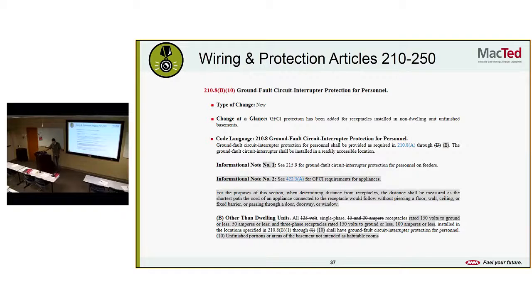More ground fault. Ground fault has been added for receptacles installed in non-dwelling unit unfinished basements. So now if you have a basement, even if it's not a dwelling unit, you have to have GFI protection in that. So all single phase receptacles, 150 volts to ground, 50 amps or less, and 3-phase. So kind of that same list. Now you need it in non-dwelling unit unfinished basements.